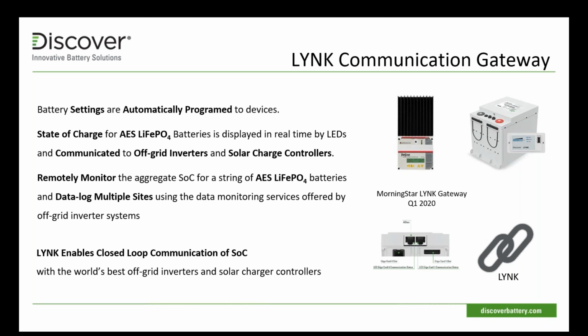What this does is broadcast the state of charge, the voltage, and temperature data to the system so that it can use that. The LYNK device additionally has LEDs on the front that give you a visual indication of state of charge. Because each of our batteries has an internal BMS, it's constantly calculating and broadcasting its own state of charge. That's a digital calculation. It's highly accurate, far more accurate than we've ever seen before in terms of SOC accuracy for battery systems. It's one of the great advantages of using these products.